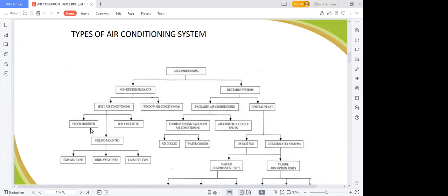Then you have the floor mounted, then you have the wall mounted. When you say floor mounted, this is the design that you see in most Nigerian banks. You see one AC as tall as your head. It discharges cooling at the top and returns all the air just beneath it. Then you have the wall mounted. The wall mounted are those ones they put on the wall. You see them mounted on the wall, but this design is fading away. So most people do not use this type, but in some old buildings or high rise buildings, you see them functioning. Then we also have what they call the ceiling mounted unit.